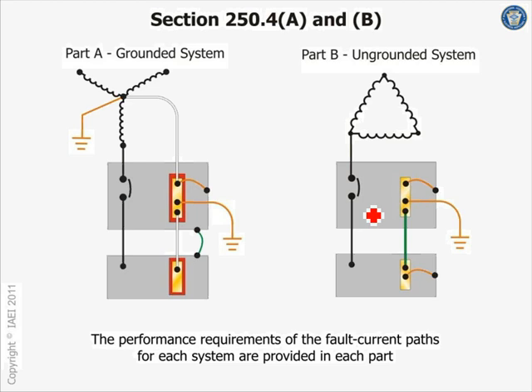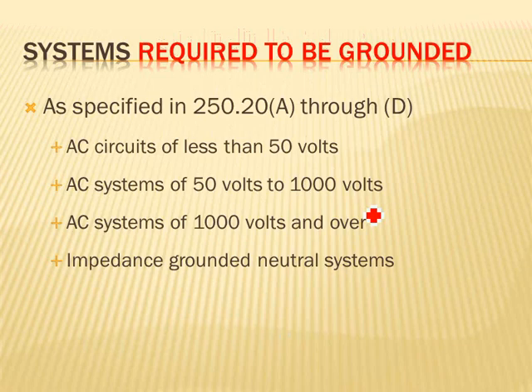Can you guys see the difference? Identical between equipment grounding is identical. The only thing is we're not bringing a neutral here. There is no neutral, and in case of no neutral, there is no bonding neutral. So look at that, very identical, the same connections. No neutral. And right here, the equipment is bonded and so forth. So there is no neutral here, there is a neutral. That's the difference between a grounded system and an ungrounded system. Okay, required to be grounded. This is interesting. Which one is required to be grounded?